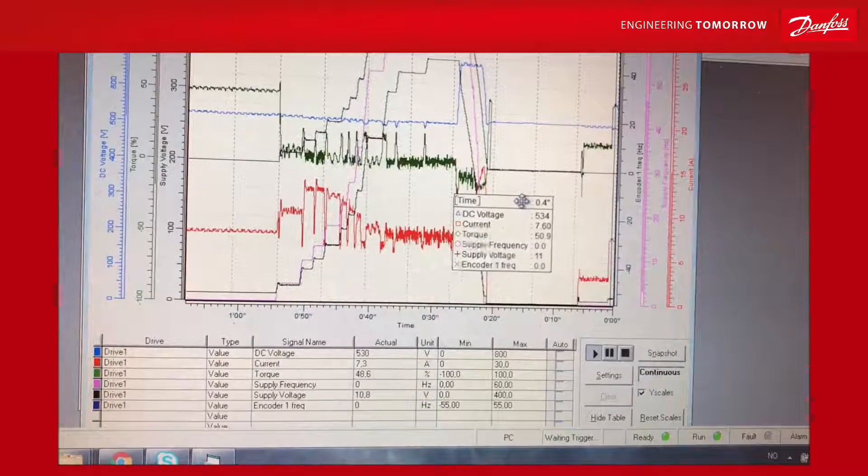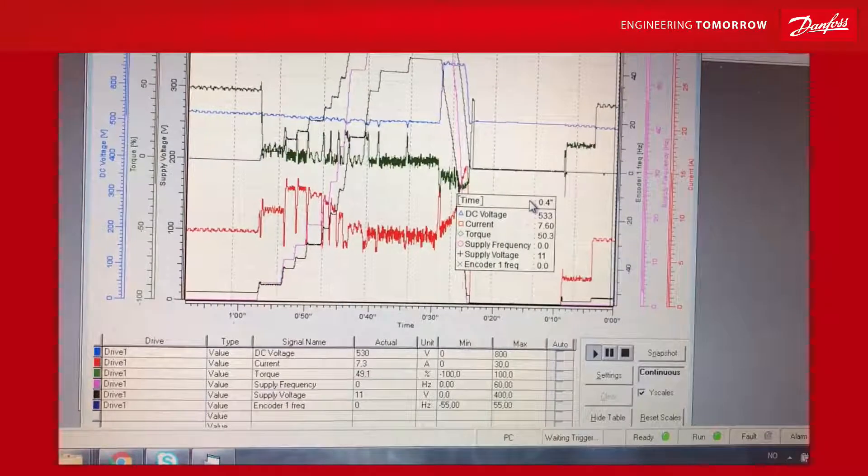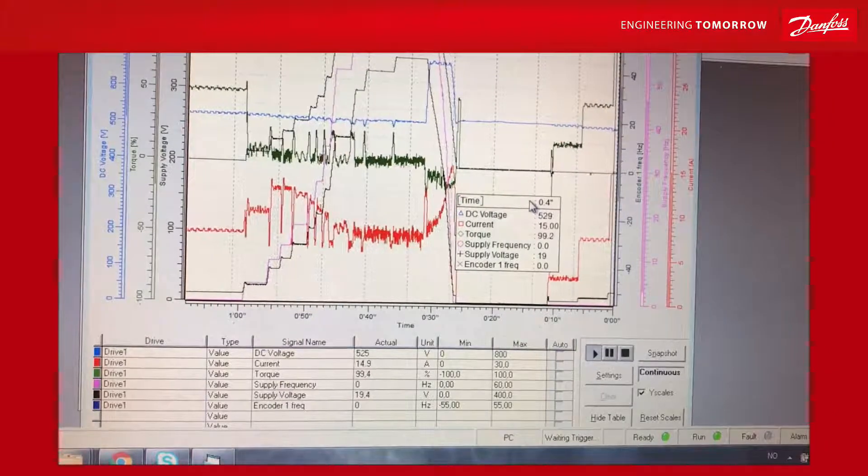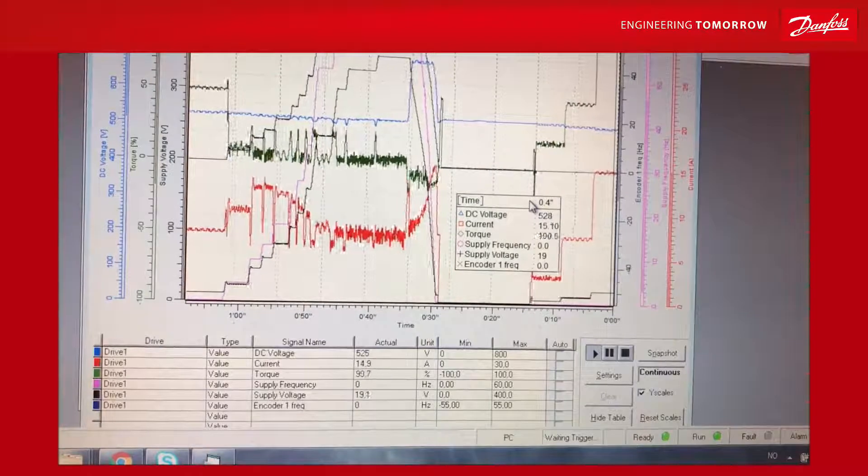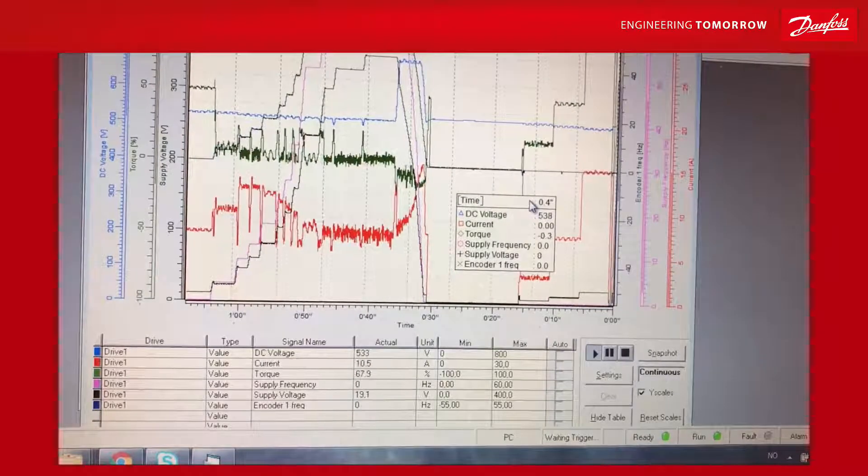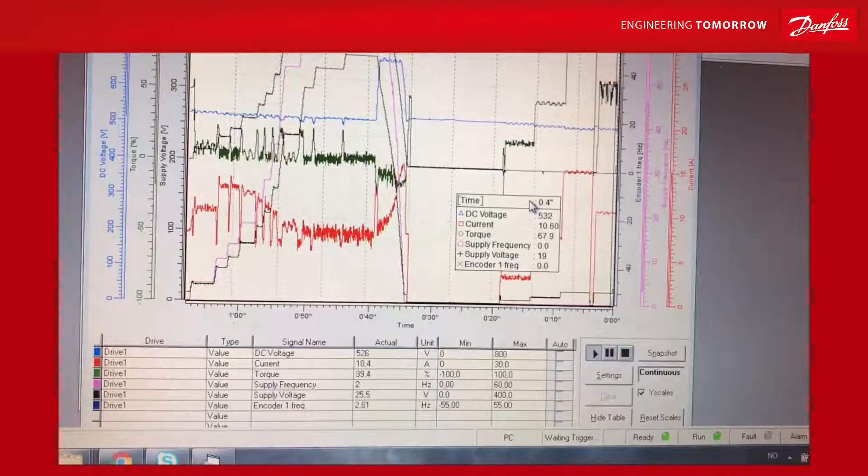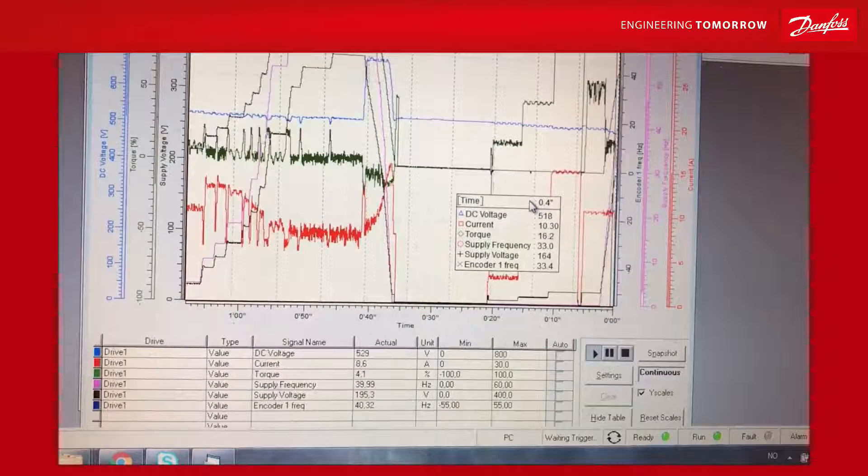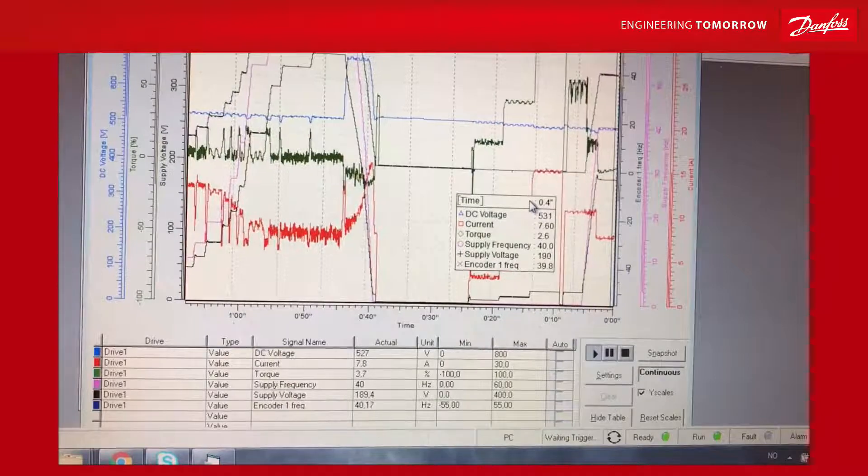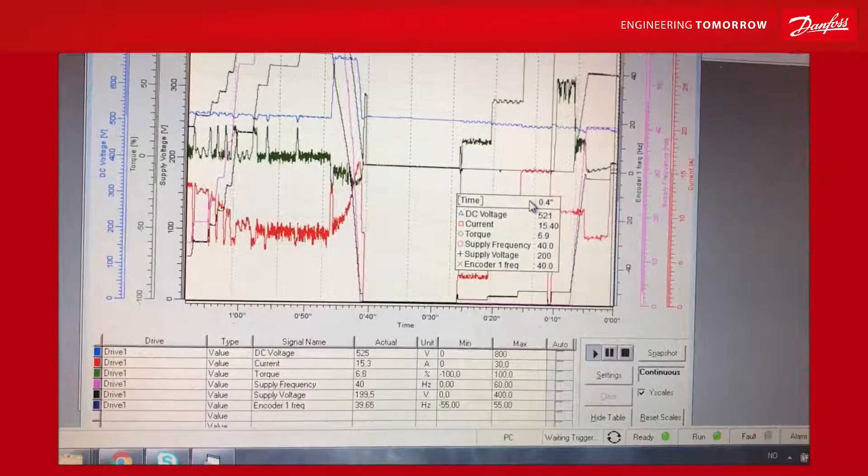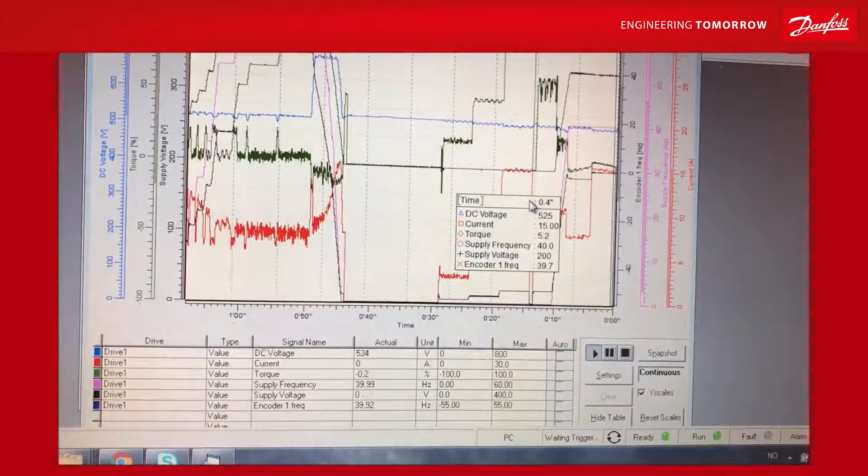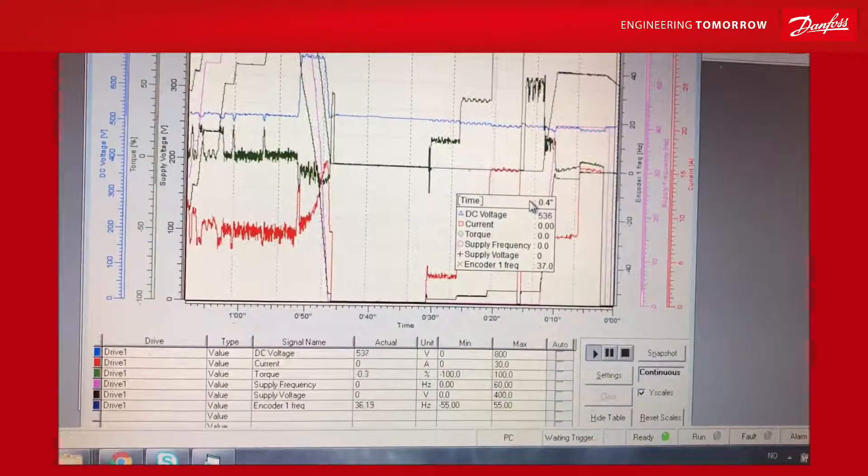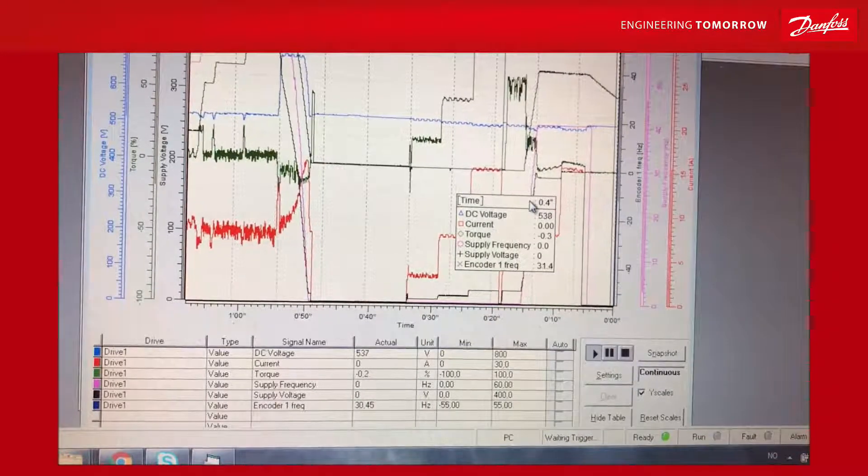First it will repeat the identification run without rotation, doing the impedance check. Then it will start rotating the shaft to identify the back EMF curve. We're seeing it rotate the shaft and measure what kind of voltage is coming back from the generator. Okay, it was already happy with that one. Sometimes it takes longer.